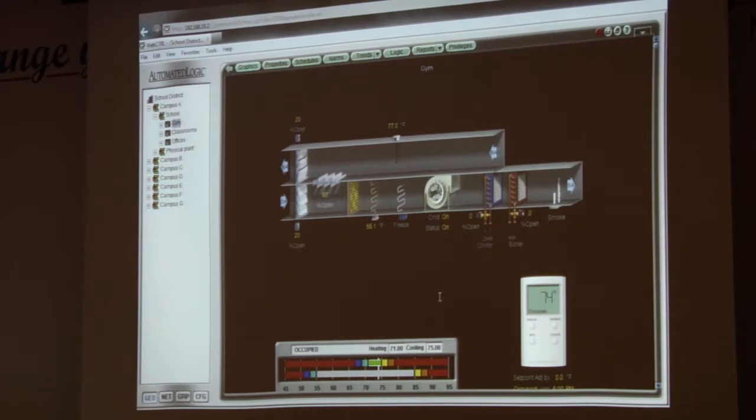So I showed you one where I left the window open, I hit apply, I locked something, I went out into the field to go check it, or I'm standing next to the air handler with my laptop or my tablet, and I check something out and I lock it, okay? This is all part of checkout. And on this one, I say, well, I've got to change the current sensor, but in the meantime, I could go ahead and get this air running, get some cool air going, knowing, of course, that you have to stop a fan to change the current sensor, right? We don't change those live.